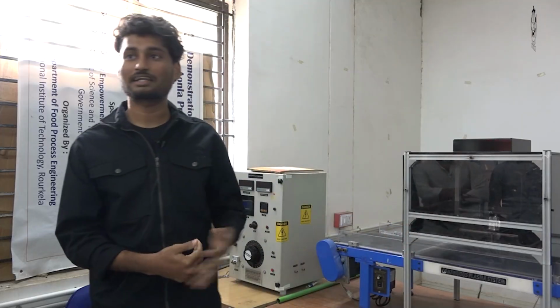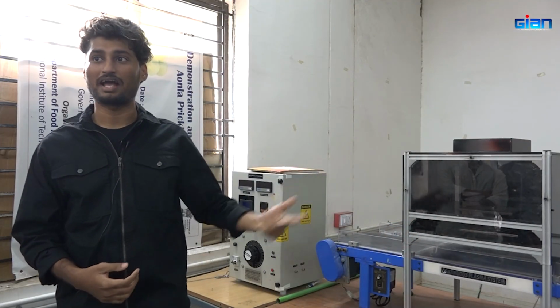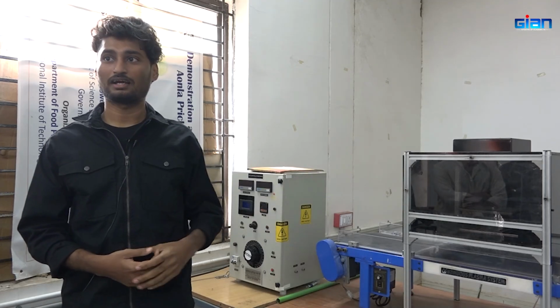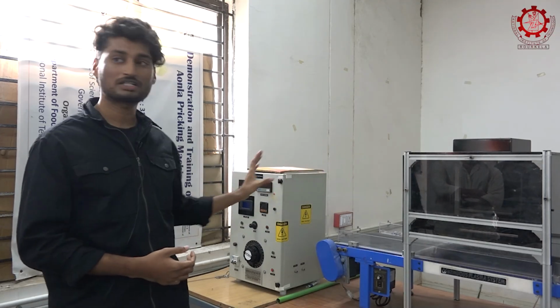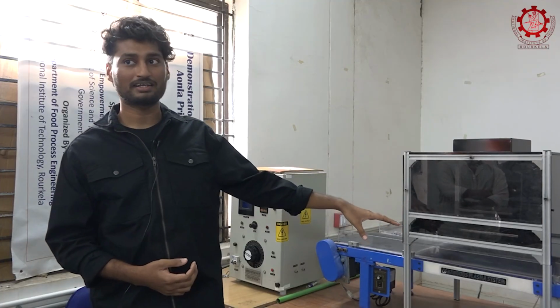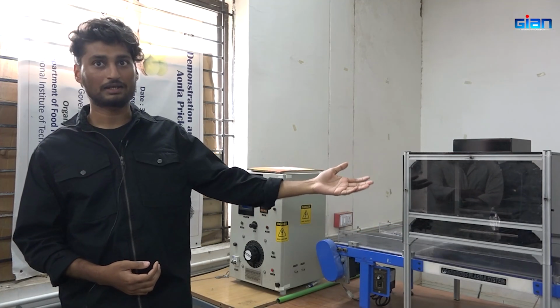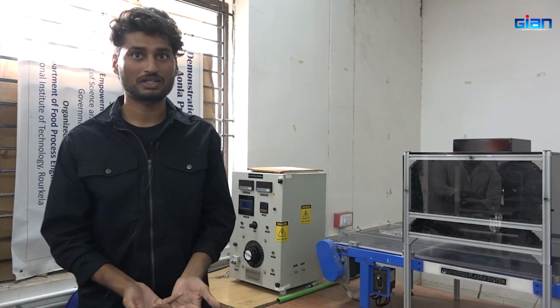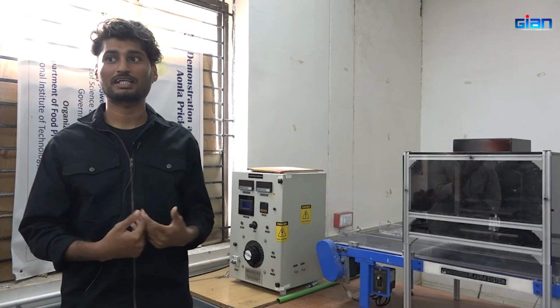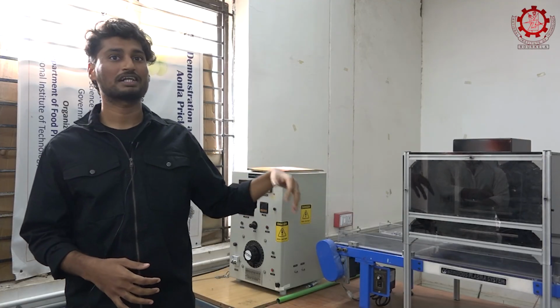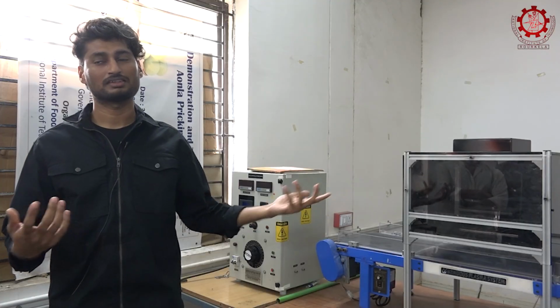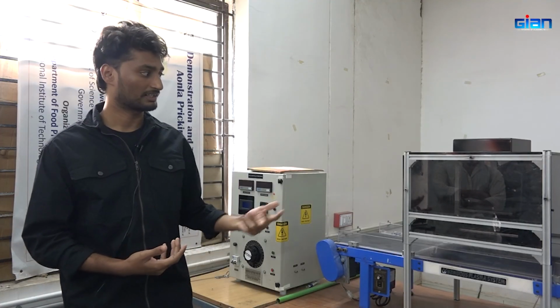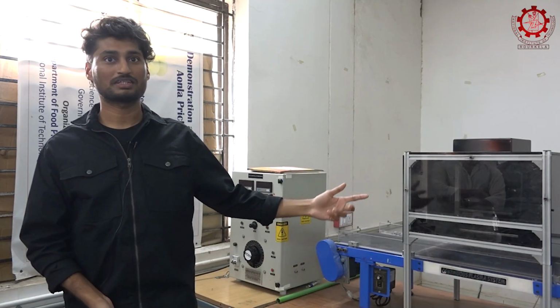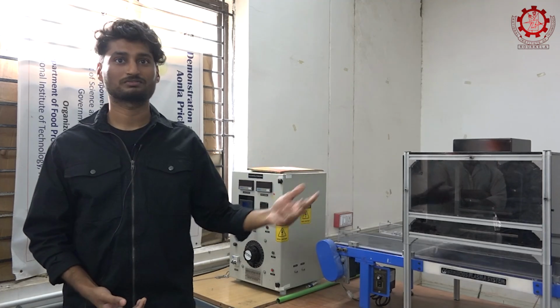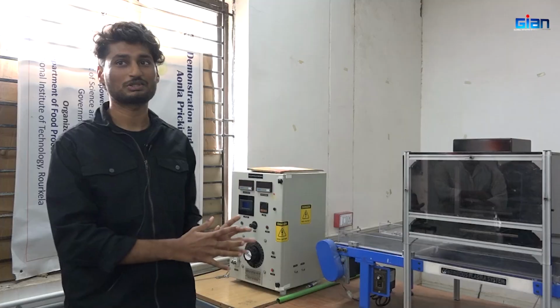It's called dielectric barrier discharge. Along with the two electrodes, it has a dielectric barrier. Let's say we have two electrodes and we are sending a high voltage. What happens if there is no dielectric barrier? The charge accumulates at the top electrode, and the electricity won't be able to pass to the gas. So the barrier acts as an insulator and helps in creating a stable plasma. That's why it's called a dielectric barrier. Normally this barrier is made of ceramic or quartz. Most commonly quartz is used, and always the ground electrode is grounded. So when something fails, it transfers the high voltage to earth, so that the person operating will be safe.